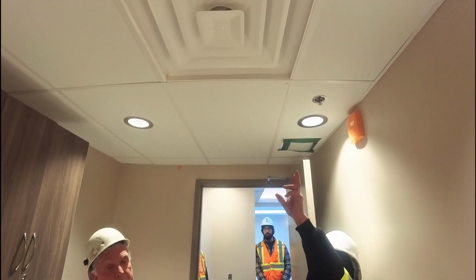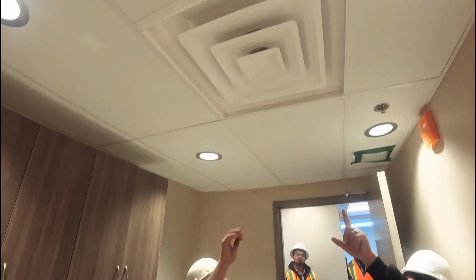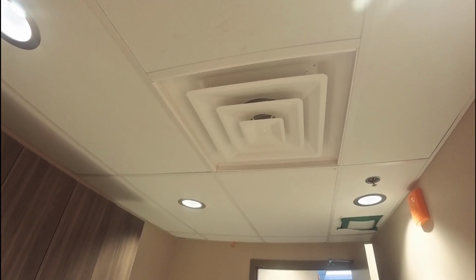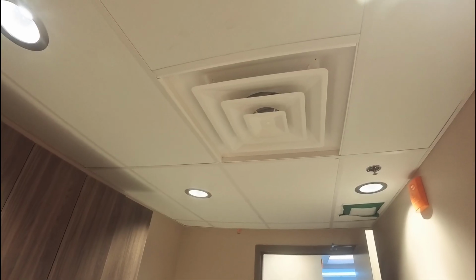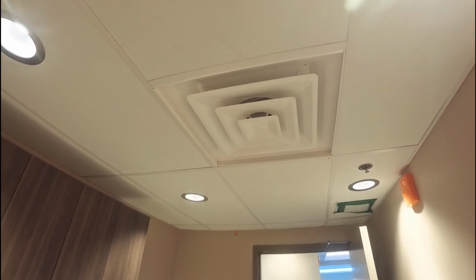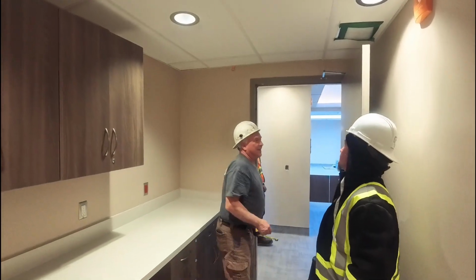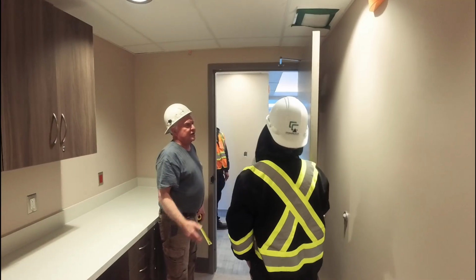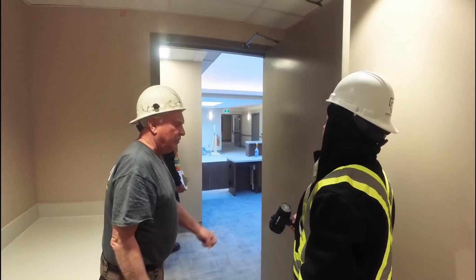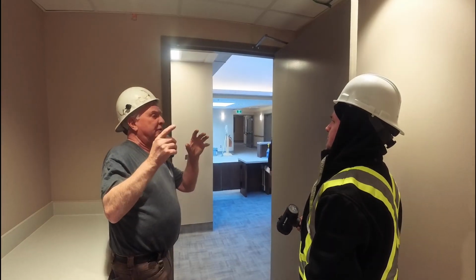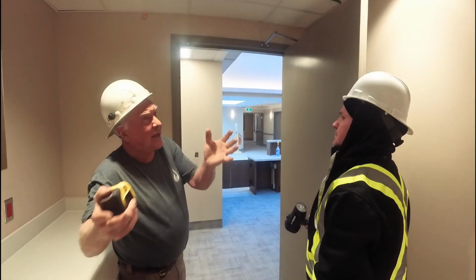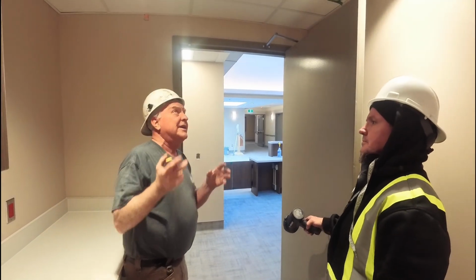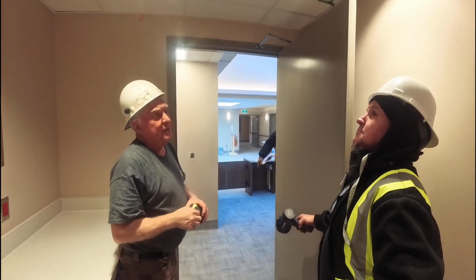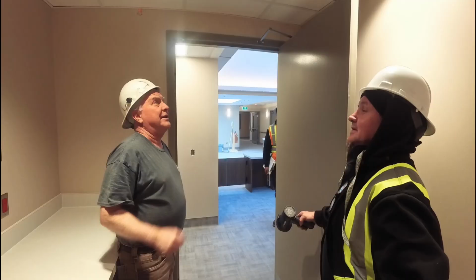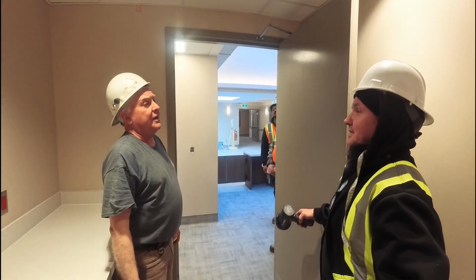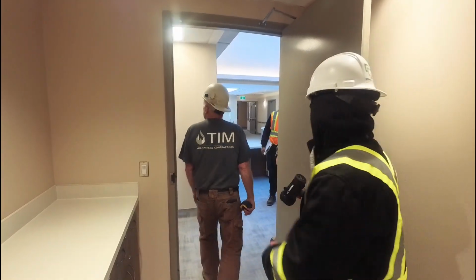Right. These ones are difficult to move around, are they? Yes, that's a little bit difficult, because it's an aluminum, soft, flexible duct that could be easily ripped or dislodged, so try not to. Sometimes, don't get me wrong, it's sturdy enough. If you look up above the ceiling and you see a little bit of play in it, you can move them, say, halfway out of the hole without disturbing it, at least enough for you to get one arm up in there or your head. I'm not saying they're totally unmovable. Yeah. I'd have a look at it from a better location first. And see if it looks good for you. Alrighty.